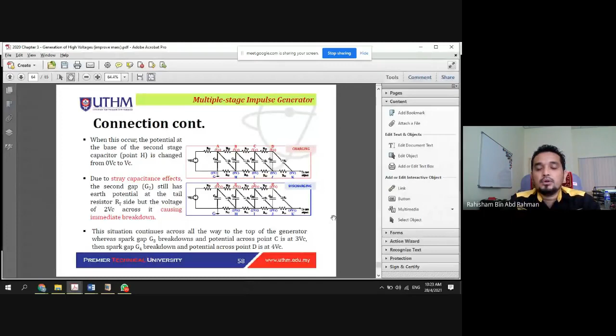And a quick note about the damping resistor. As I mentioned, it is to control the oscillation in the voltage waveform, because we want the waveform to be nice - we don't want noise and oscillation within the waveform. That's why we use the damping resistor. As I mentioned, the damping resistor is 40 ohms, compared to RT which is 500 to 700, so its value is far lower than RT. This is the use of the damping resistor.